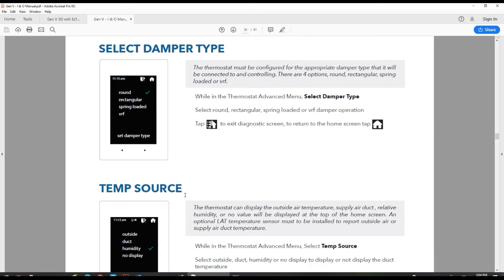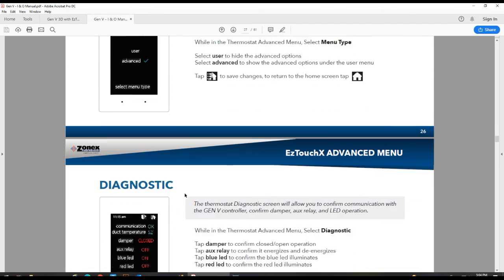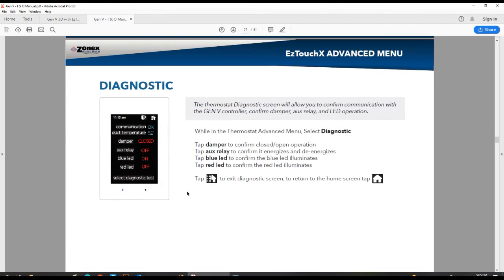Alright, the last feature here is diagnostic. This is a great tool to utilize on the zone thermostats. So when you go into diagnostic mode, it is going to put the stat into a test mode. It will confirm communication with your Gen V controller. But the big thing is it will also close your damper, or if you want, you can open the damper. So when you do this, it will apply 24 volts for about 60 seconds, and you'll be able to confirm that the damper is running open or running closed.